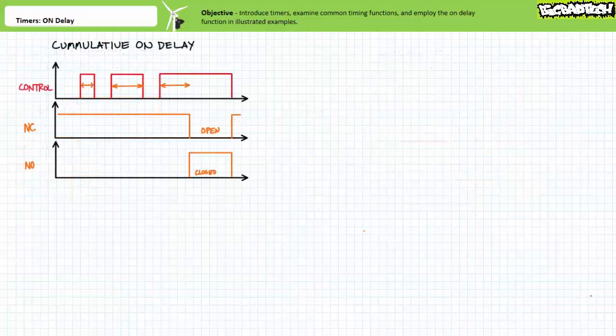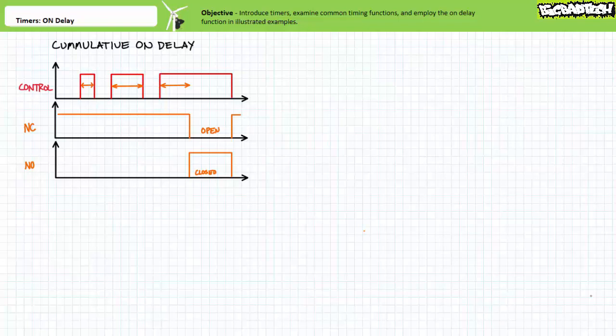Finally, the cumulative on-delay timer is a record-keeping function where the timer does not temporarily shift the outputs, but rather keeps track of how long its controlling input has been energized. Only after the controlling input has been asserted for the predetermined period of time do the outputs respond. Despite the controlling input being discontinuously energized, once the timer has accumulated the required delay period, the contacts switch to their activated opposite states. Such a timer could be used to keep track of how long a particular controlling input has been asserted and alert the system that some maintenance or other task must occur.